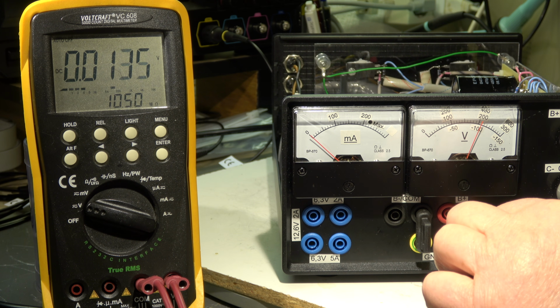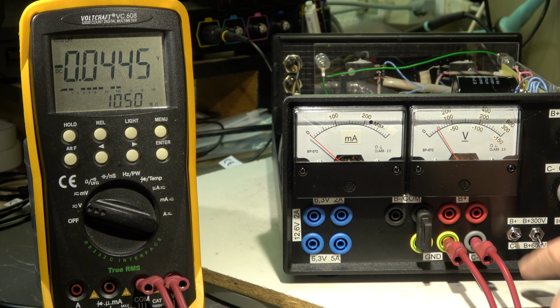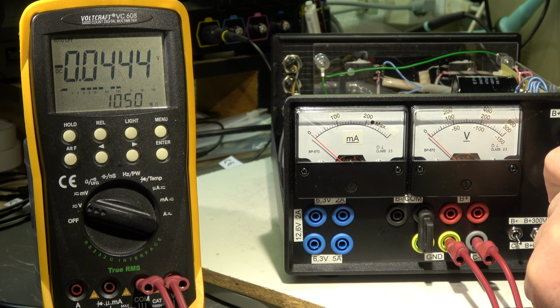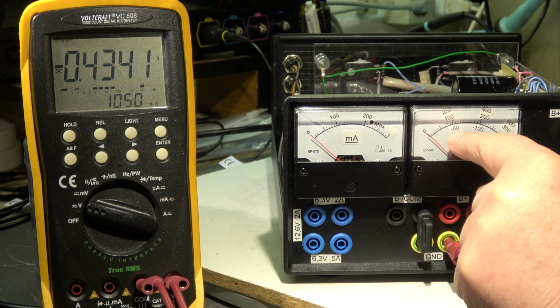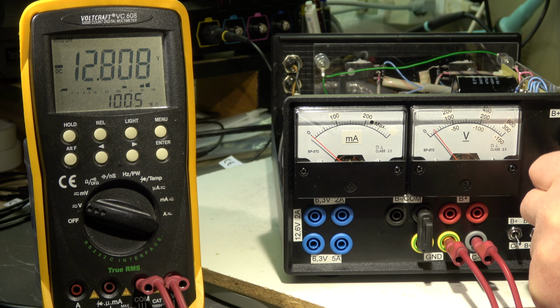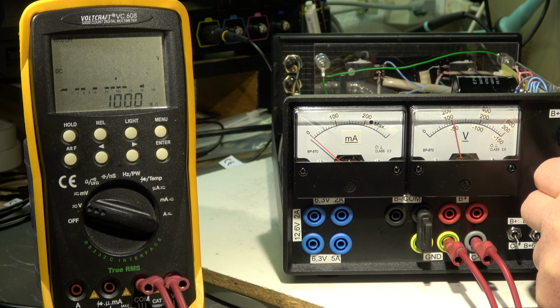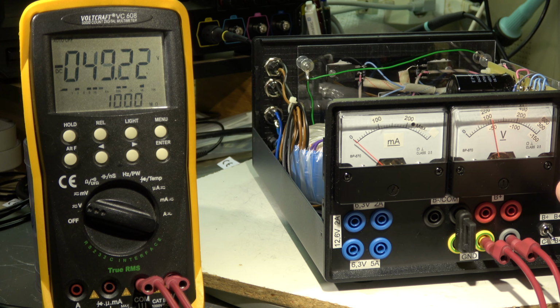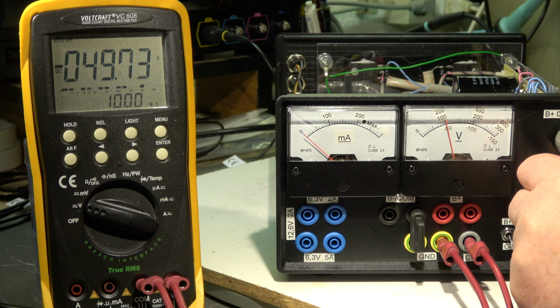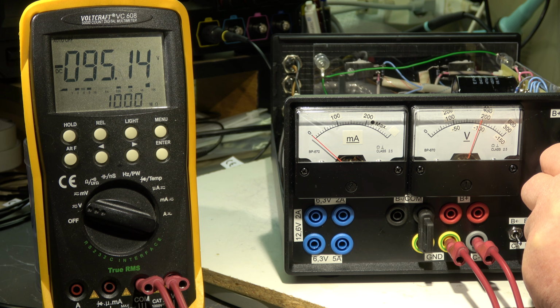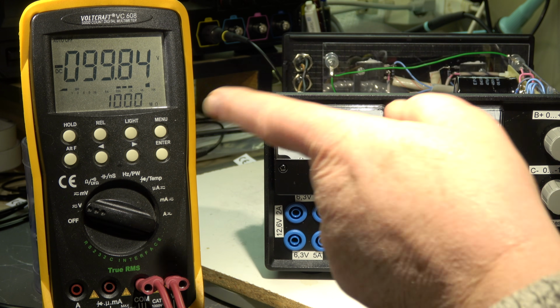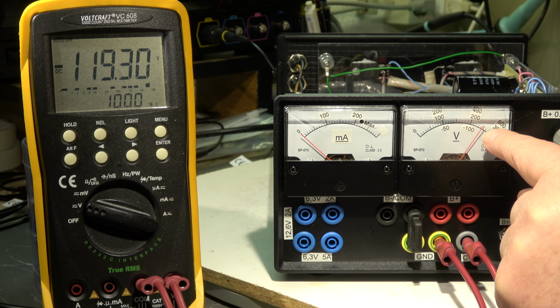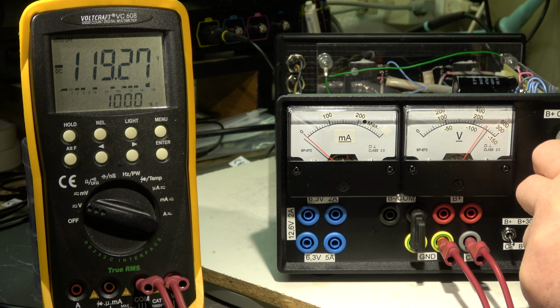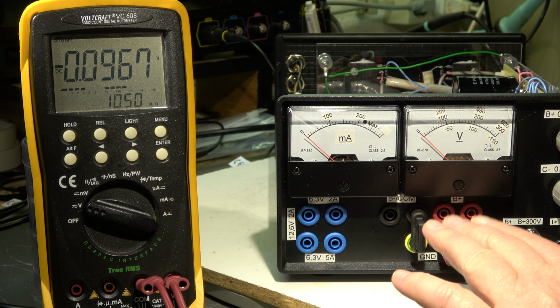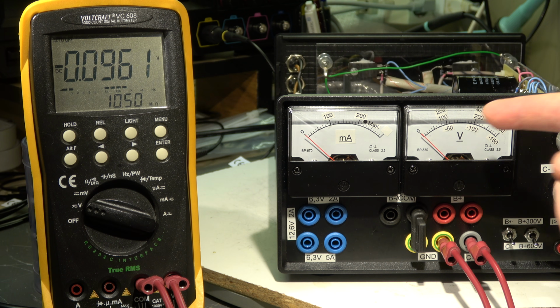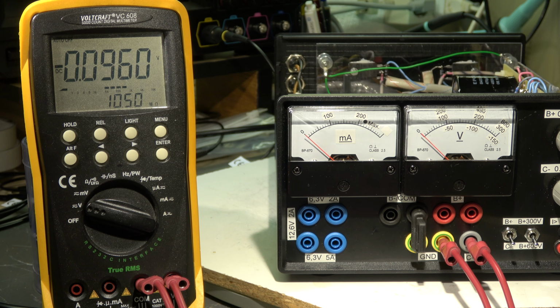Now let's check the C minus output. I go with the meter to C minus, negative, minus 50, 100, 150. So at minus 50, is it minus, yeah, okay, minus 100. Okay, and minus 120, that's the maximum. 119, that's also okay. This voltage, of course, is very weak, and even the load of the instrument is too high for it.